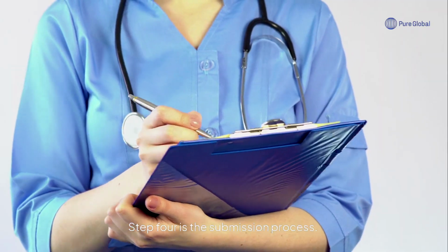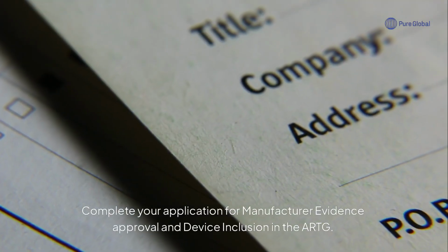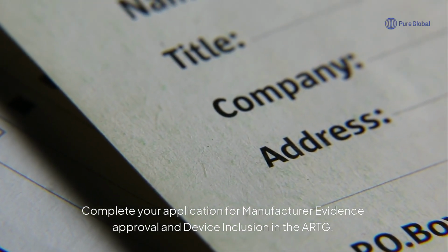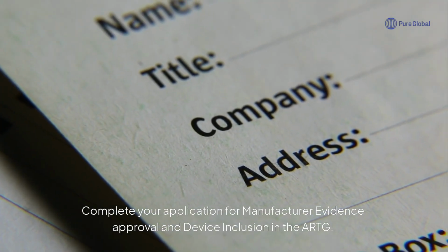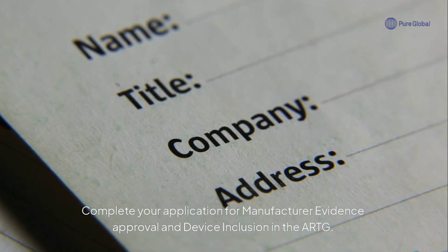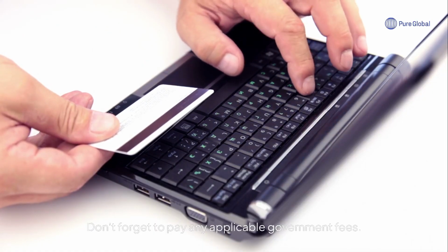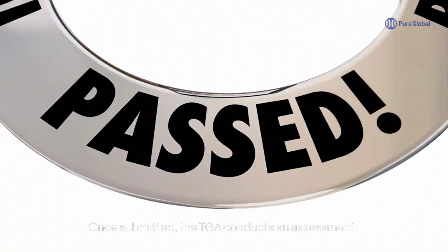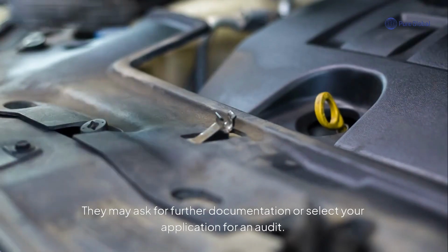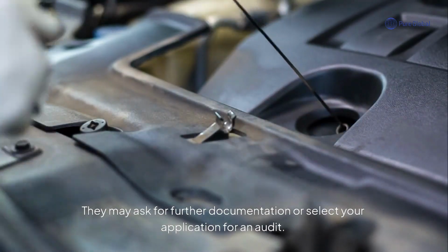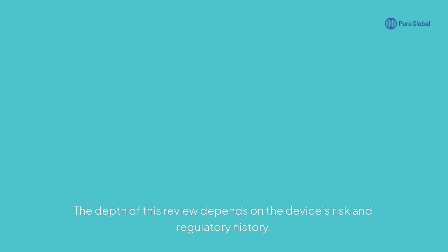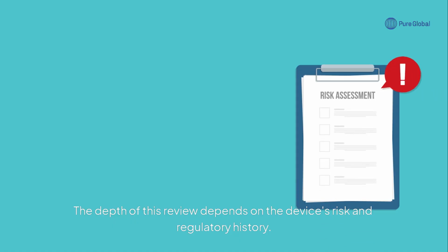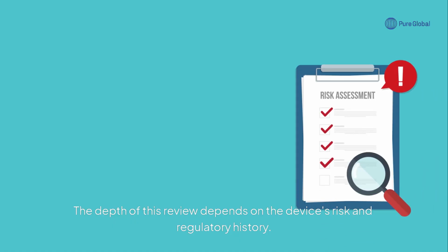Step 4 is the submission process. Complete your application for manufacturer evidence approval and device inclusion in the ARTG. Don't forget to pay any applicable government fees. Once submitted, the TGA conducts an assessment. They may ask for further documentation or select your application for an audit. The depth of this review depends on the device's risk and regulatory history.